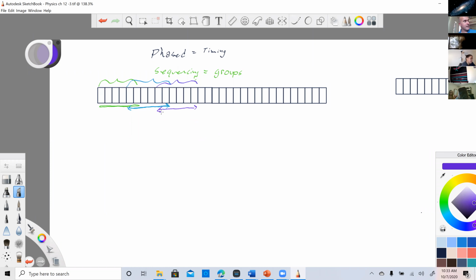Remember on page 180, the subsetting beam steering does not describe steering. Because it says with a linear sequential array, a small group of crystals are fired simultaneously to create a sound beam. The sound beams are parallel to each other and are typically directed straight ahead, which is kind of the opposite of steering, right? So just keep in mind that one is mislabeled, I would say.